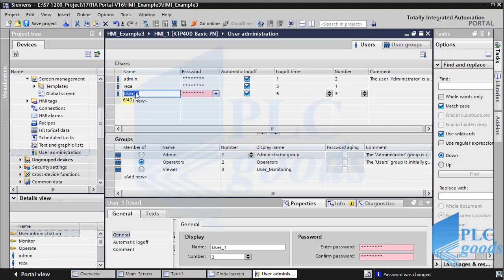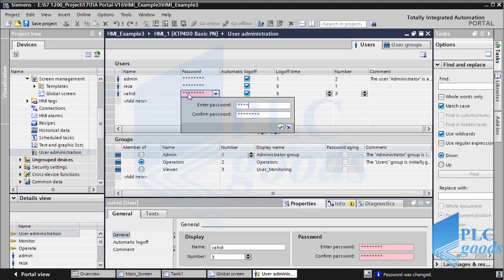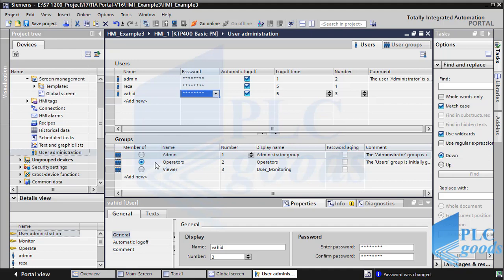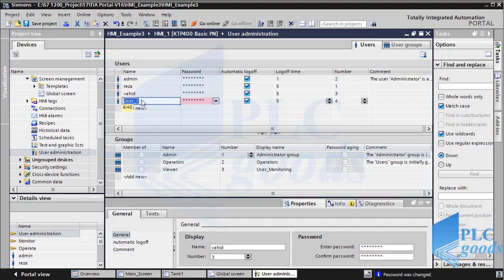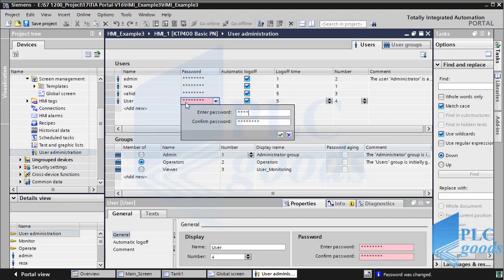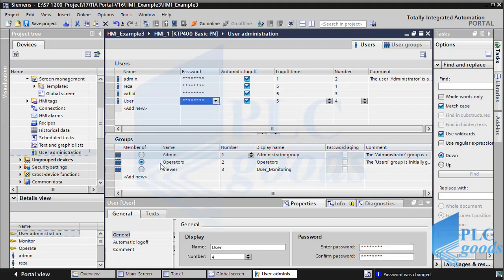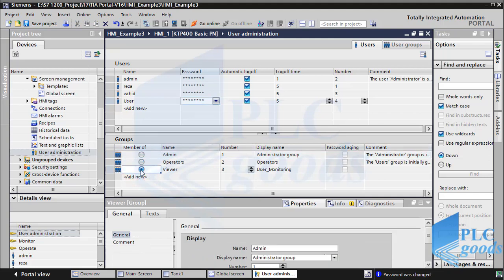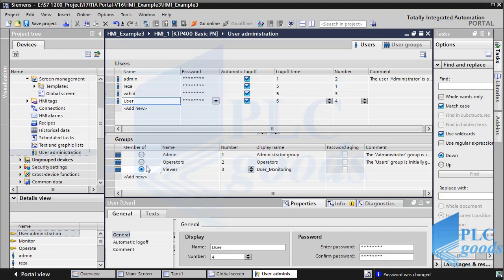Let me define another user. This user belongs to operators group 2. Let's insert another user — I'll change the last user's group to viewer. So here we have one admin with full accessibility, two operators, and one viewer. Here we can also determine a time if automatic log-off is enabled. For example, if the admin does not do anything for one minute, the HMI will automatically log off that user.